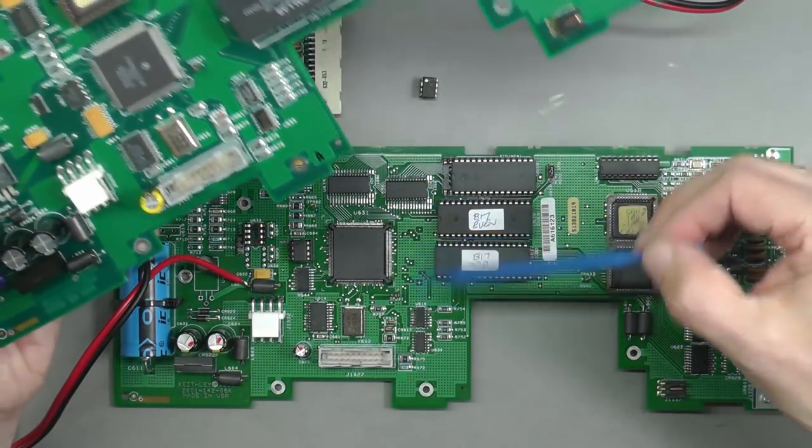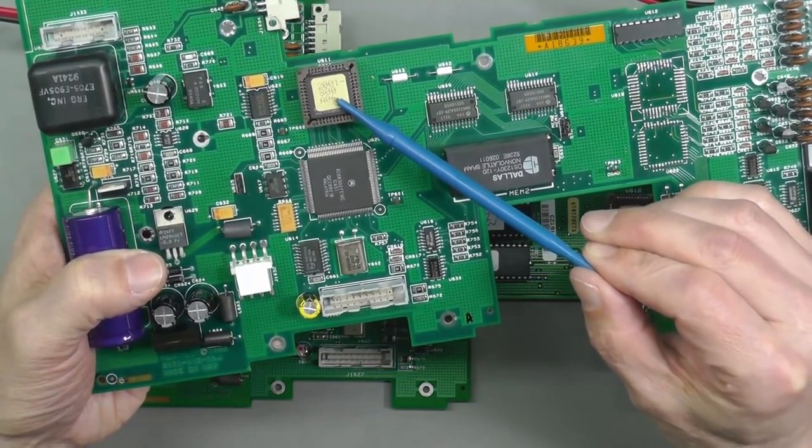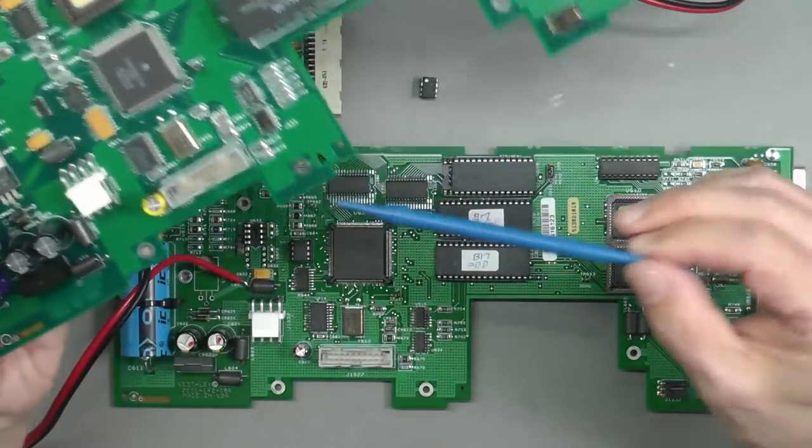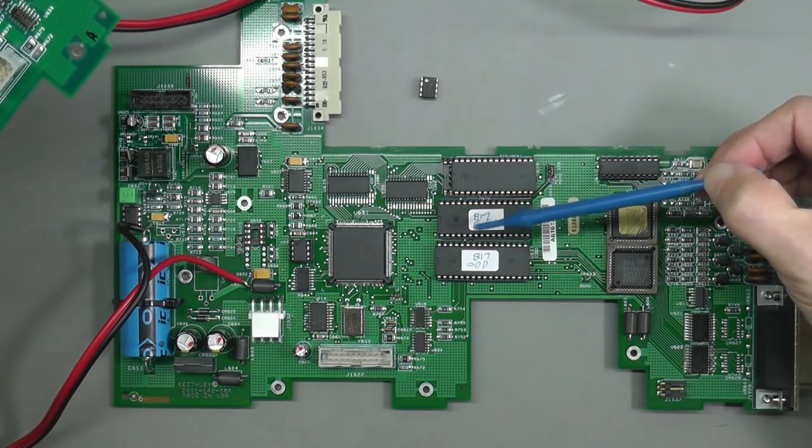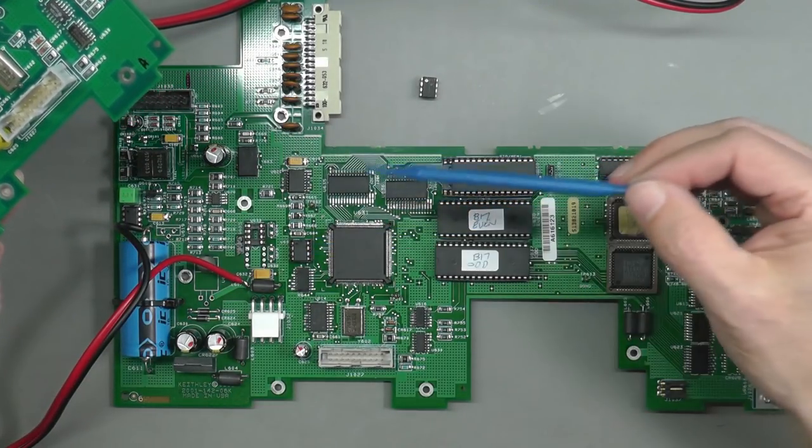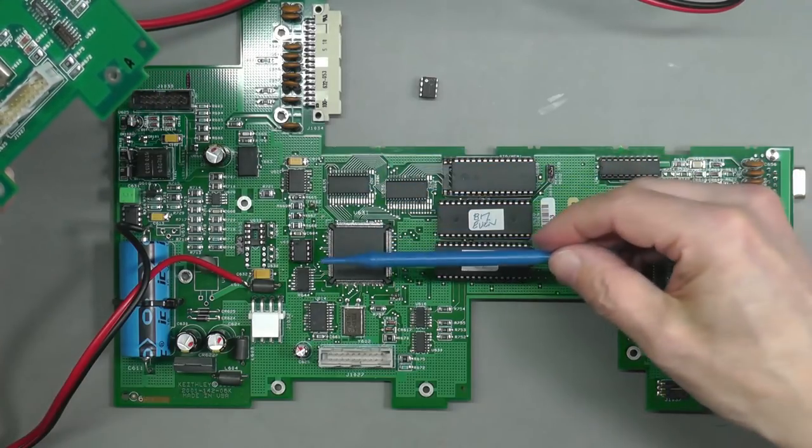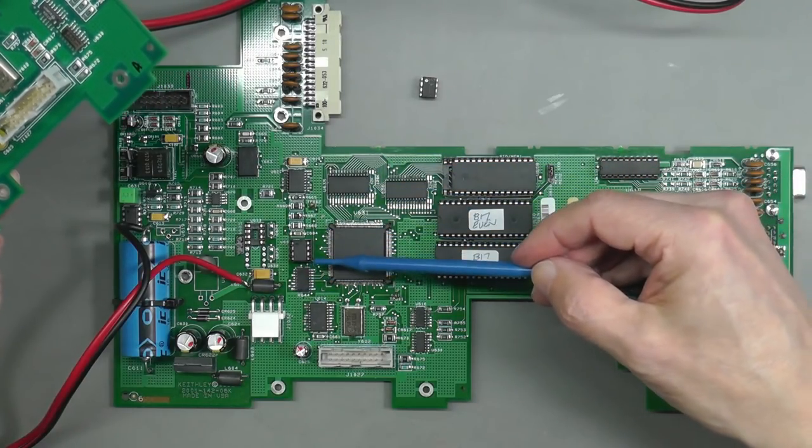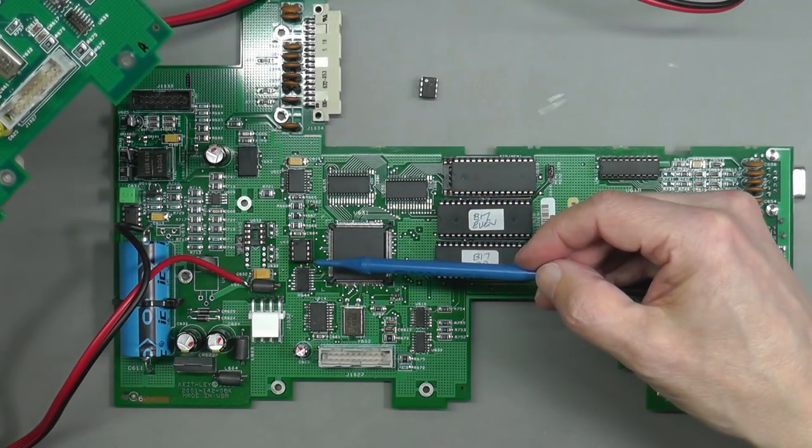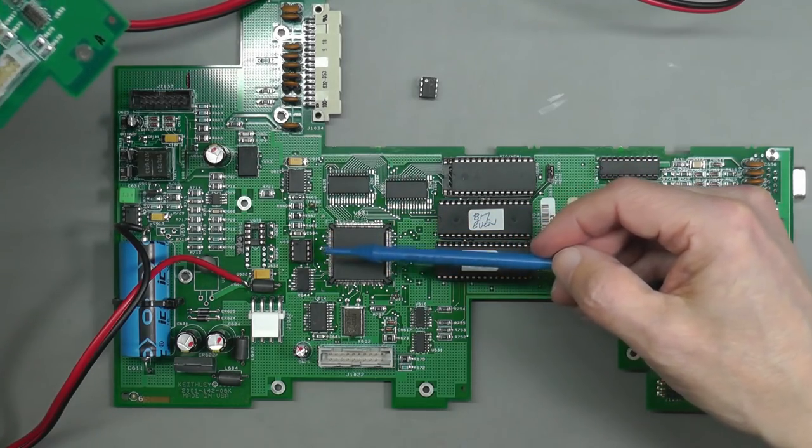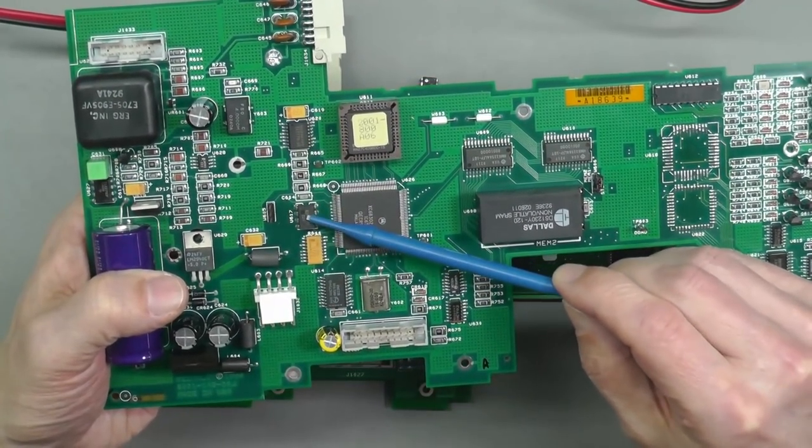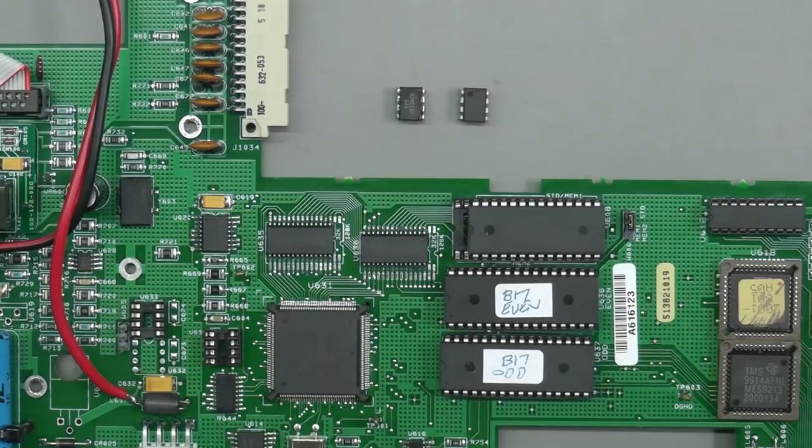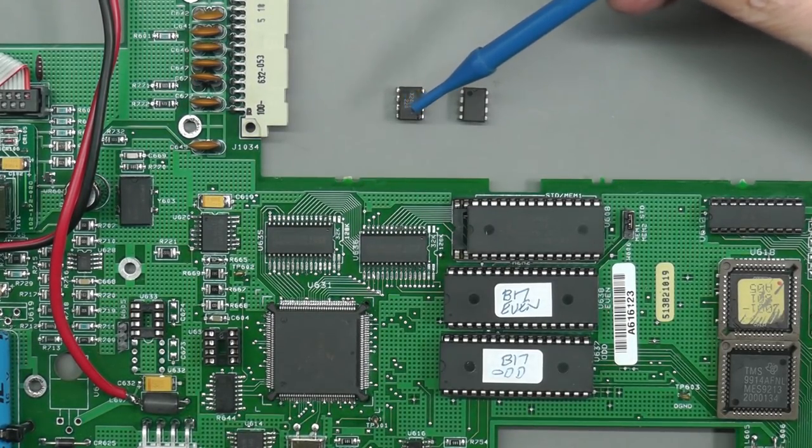The firmware version that's fitted to this board and this one here, I think this one here's got A06 fitted to it firmware for the main CPU, whereas the new one of course I programmed B17. So whether that calibration data is entirely compatible I'm not sure, but there's no harm in doing it. I've got a socket in place anyway on the chip so it's easily removed and replaced with a new blank one or whatever. So let me go ahead and remove this chip from this board and read it into my programmer.